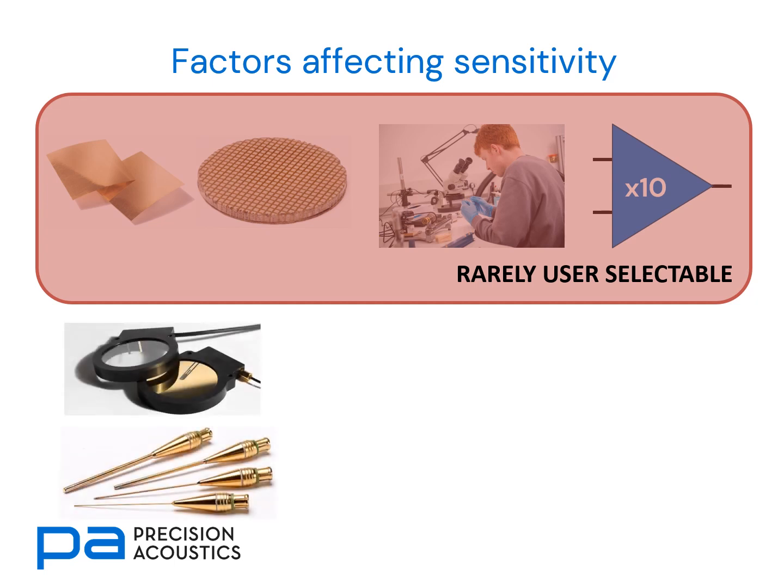The constructional type may have an influence on sensitivity. Specifically for probe type hydrophones, where there's a pressure reflection from a rigid boundary, this can cause pressure doubling. So all things being equal, the same size hydrophone that's a needle can often be expected to have twice the output of a comparable membrane.